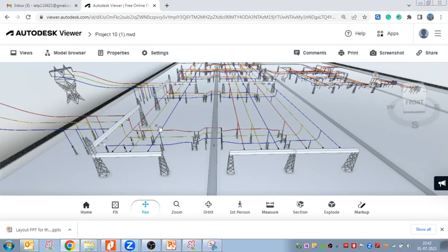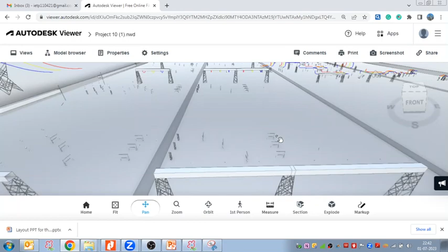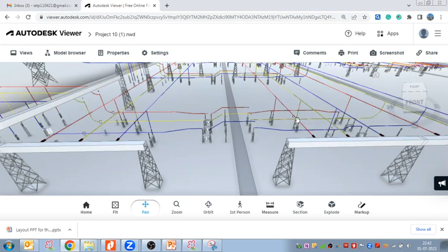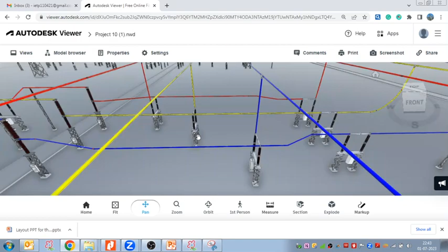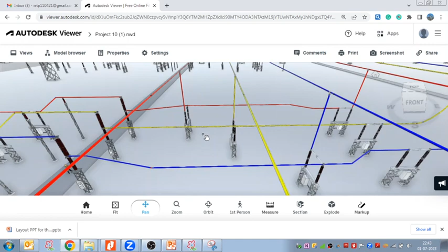In that case we use the tandem isolator or the diagonal arrangement of the isolators to reduce the space. Here we are taking the flexible isolators, a simple arrangement of the isolator, but near the main bus bar 2 or below the bus bar 2 and below the transfer bus bar, we are putting this three phase disconnector in a diagonal or tandem arrangement, right? And by doing this, if the interconnection conductor length is increasing, in that case we can use the post insulator to provide support for this conductor. Anyway, this has been discussed during the Saturday module as well.